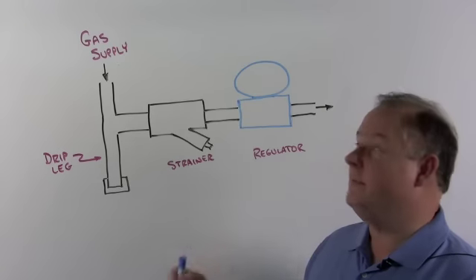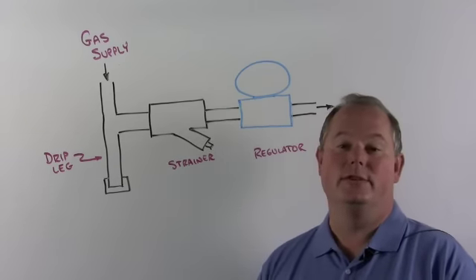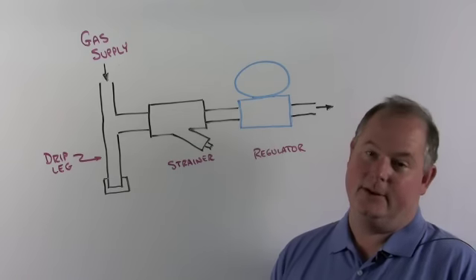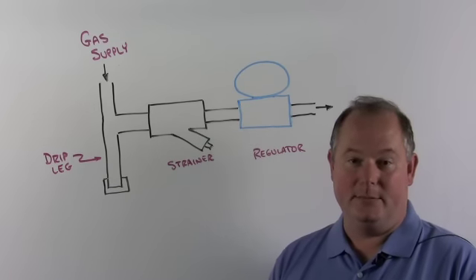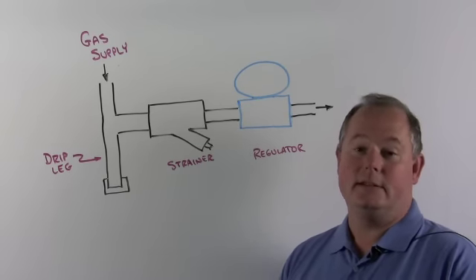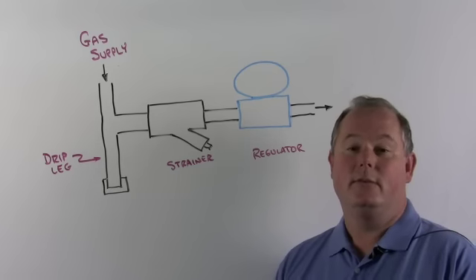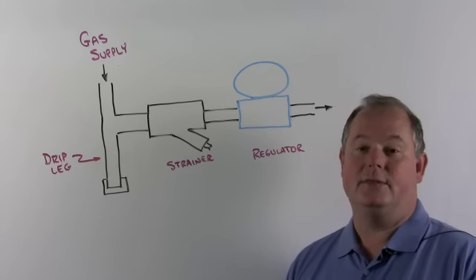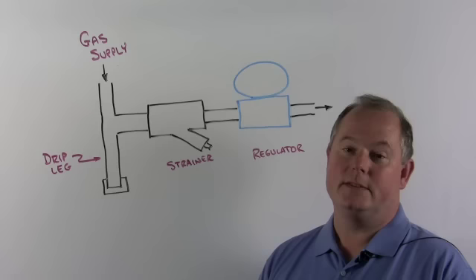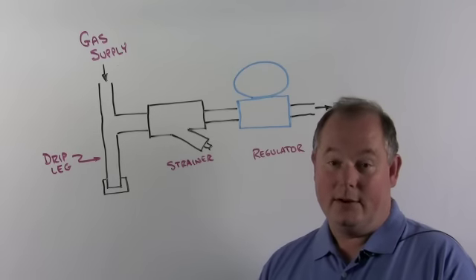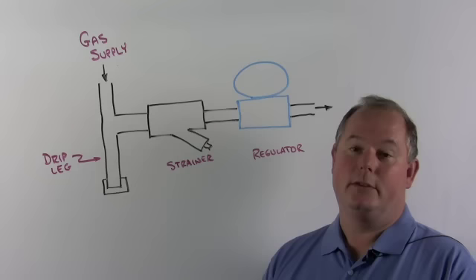Why do we need that? Because the gas supply has more than just gas in it. The gas is dirty. It's got pipe threads, pipe dope, little pieces of rust, all kinds of debris. When that debris gets in that gas regulator and sits between the soft seat and the hard seat, it's going to leak through.